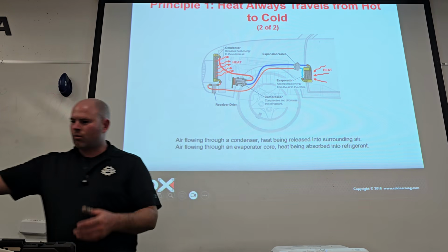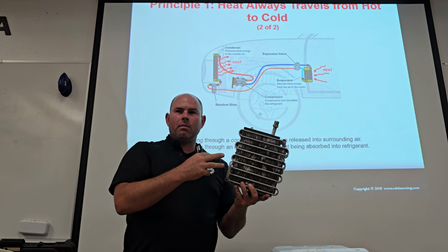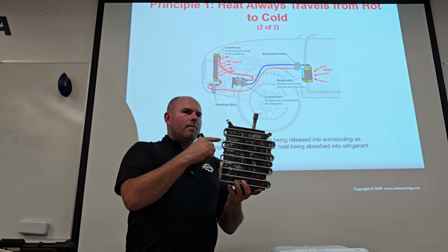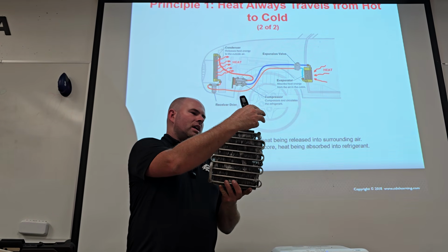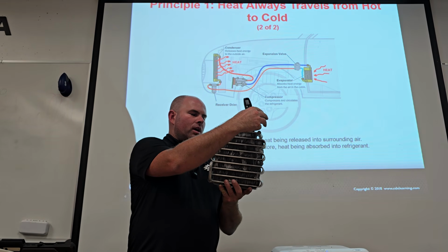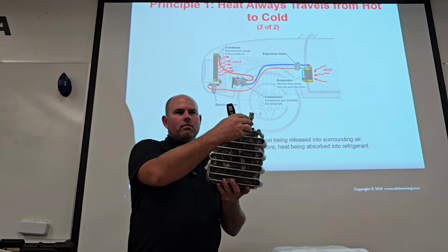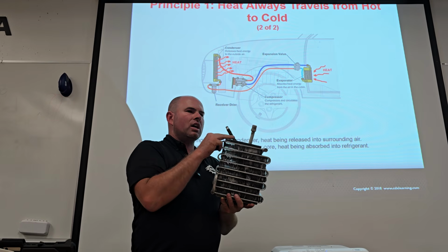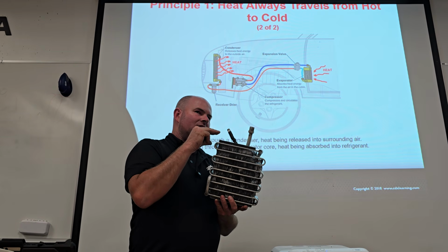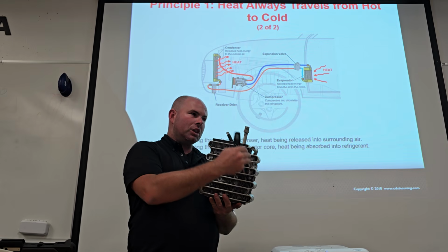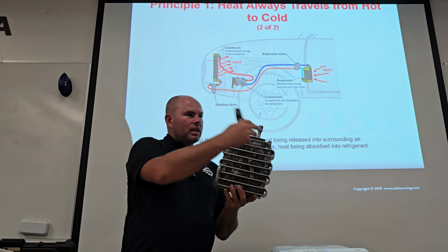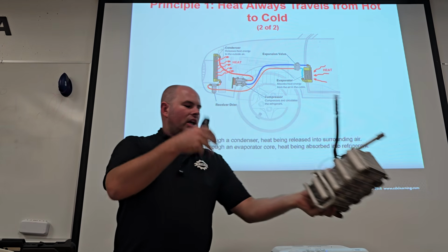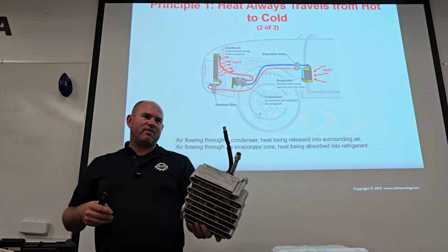But this is sized and designed in such a way by the engineers. In normal operation, you can throw as much heat as you want at this, and it'll absorb all that heat, and it'll just literally make it change from a liquid to a vapor, right? It'll just evaporate all that. It'll never actually get hotter. So the coolness to the touch is what cools the air. But the reason this thing doesn't get warmer is because it's changing state inside. The refrigerant is carrying the energy away. It's cold. This thing never warms up because it's always changing state in there, assuming you have the correct refrigerant.